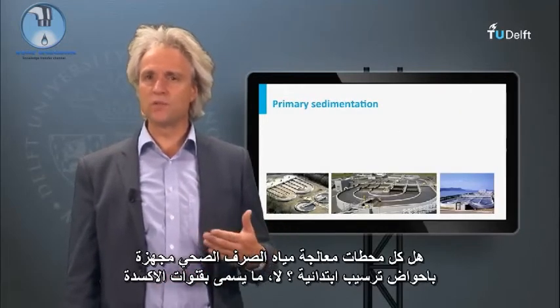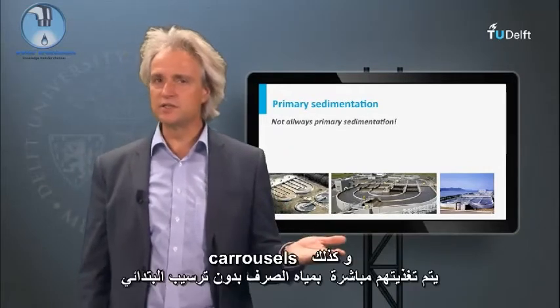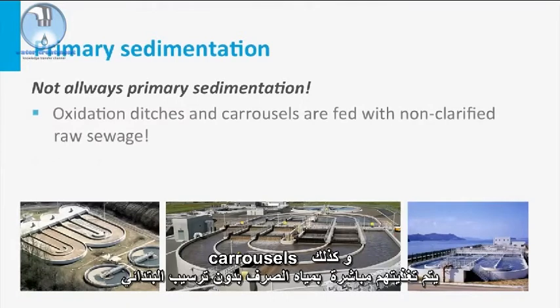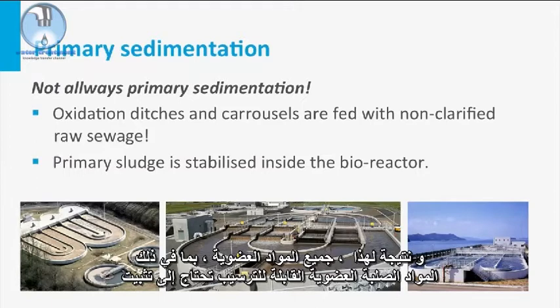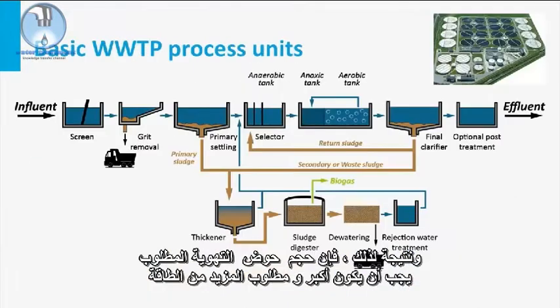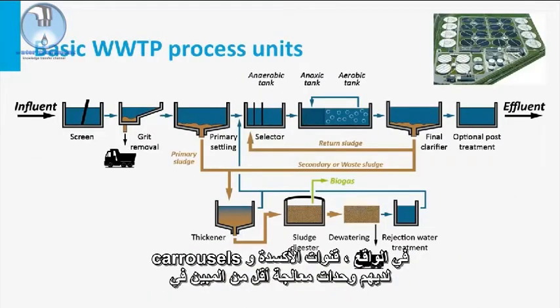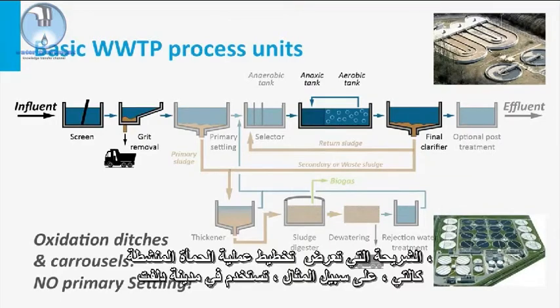Are all sewage treatment plants equipped with a primary settler? No. The so-called oxidation ditches and carousels are directly fed with non-settled sewage. As a result, all organic material, including the settleable organic solids, need to be stabilized in the aeration tank. And as a consequence, the required volume of aeration tanks needs to be bigger and more energy is required. In fact, oxidation ditches and carousels have fewer process units than the schematized activated sludge process, which is used in, for instance, the city of Delft.